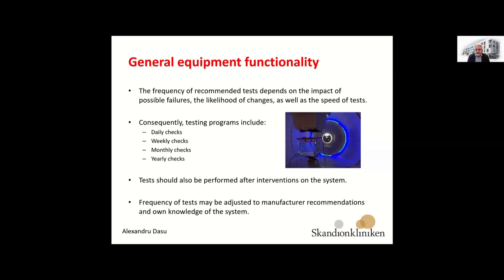For the frequency of the tests, there are recommendations that are around, but they may be adjusted according to manufacturer recommendations. As you start building knowledge on the system, you could realize that the frequency of some tests has to be increased because you see more errors in a certain part or a certain test, and you want to ensure good performance. Or you see that you do not have major drifts in some parameters, and therefore you could check them less frequently, in order to see that you are still within the tolerance parameters.